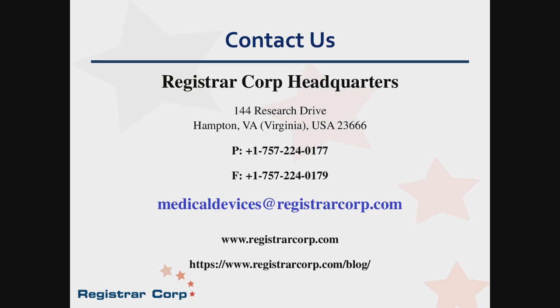For contact lenses, will the UDI have to be on every blister pack in the box, or can it be located on the outer packaging? That's a very good question. Actually, contact lenses at the moment also have an exemption on the compliance dates. There is a letter especially for contact lens manufacturers, because your industry already has something in place that is very similar to the UDI, and FDA is looking into how they can use, or if there's a possibility to use, that number system that you have in place already as a possible UDI, but no decision is made at the moment. If you would like to send us an email, we can send you these letters that grant you the extension on the UDI.